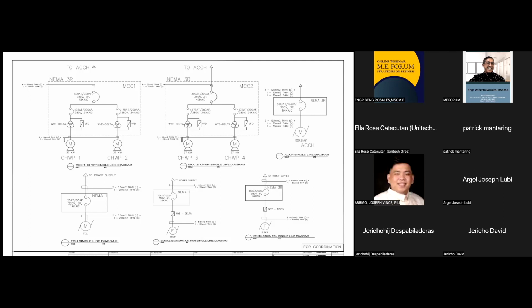So individually, each motor, like our chilled water pump, has a Y-delta and VFD starter. The question is, can the Y-delta stand alone without a VFD? The answer is yes. A Y-delta is a soft starter. It helps in reducing the inrush current and the starting current. Like I said earlier, the starting current is 10 times the normal current rating. With the help of the Y-delta starter and the VFD, it actually limits your starting current, preventing high power usage.